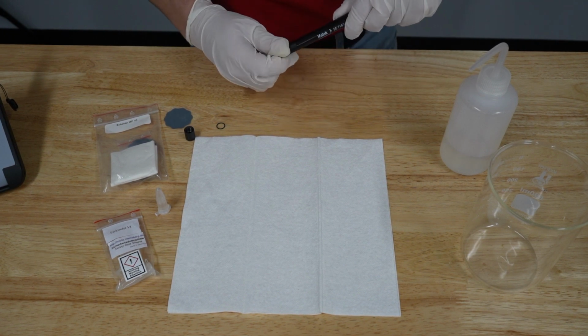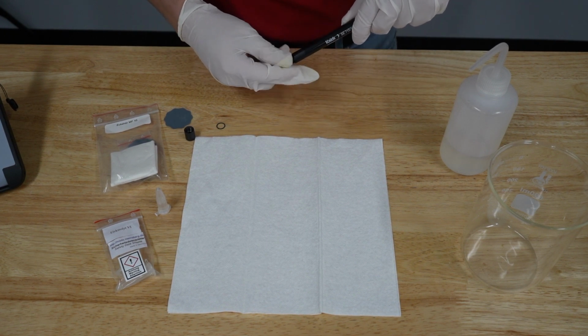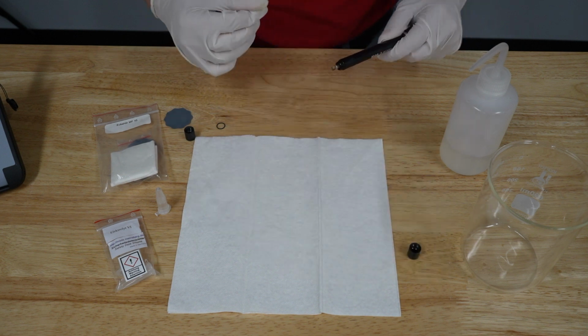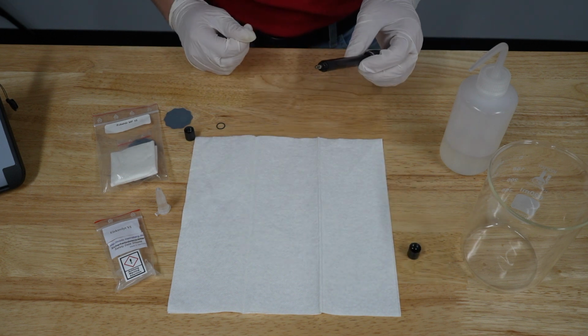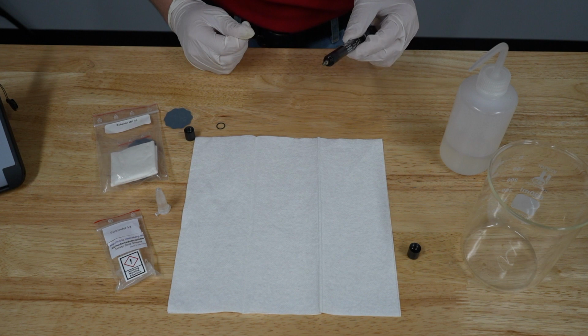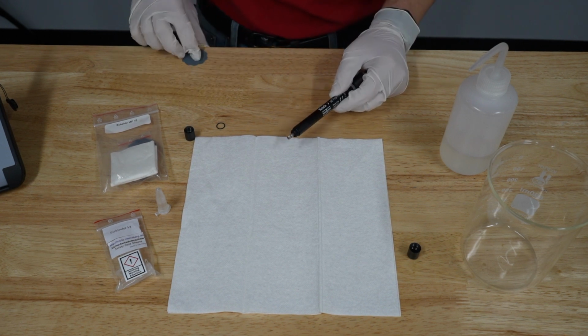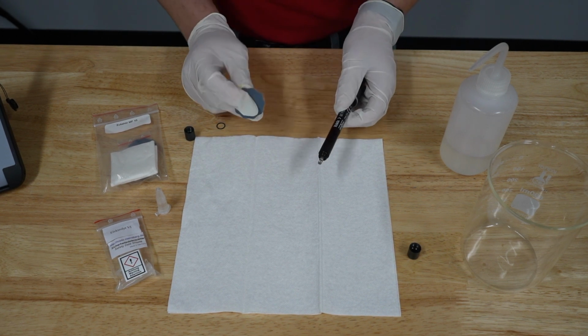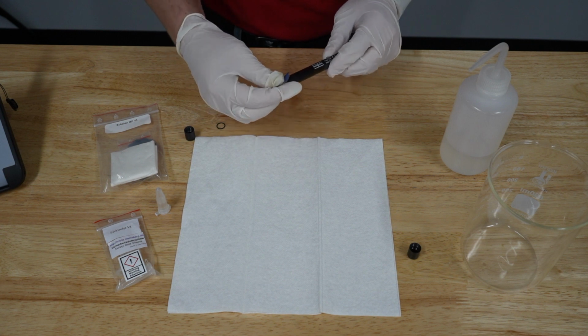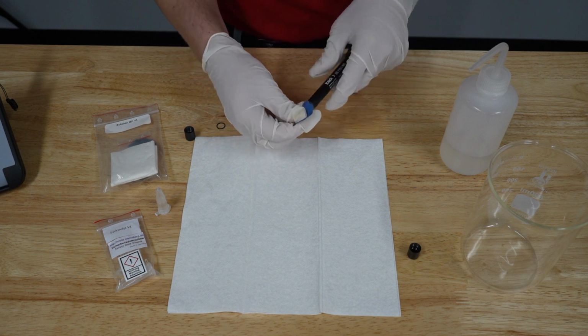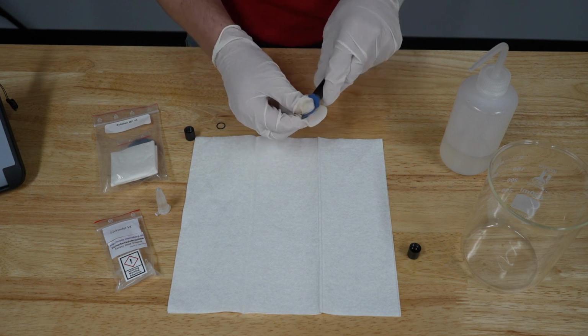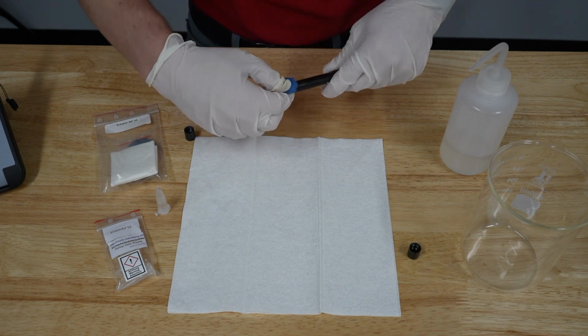To begin, I'll remove the cap and set it aside. The O-ring on this sensor is intact, so I won't be replacing it, but I'll use the sandpaper patch to get any residue off the end of the sensor, making sure it's completely clean before putting on the new cap.